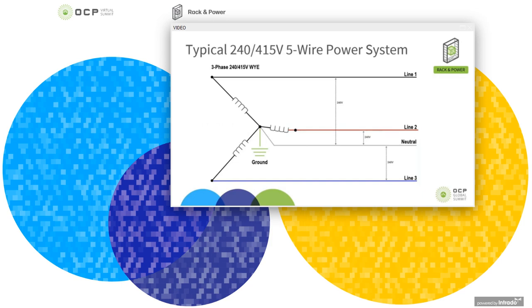In a 32 amp Y system, for example, we can get about 23 kilowatts out of a 32 amp feed. Now, best practice, that's derated to about 18.4 kilowatts. And in the U.S., a 30 amp application, 30 instead of 32 amps, will yield about 21.6 kilowatts, but still derated, that's about 17 kilowatts. So we're talking about 17 to 18 kilowatts of available usable power in the rack with a reasonable amount of overhead.